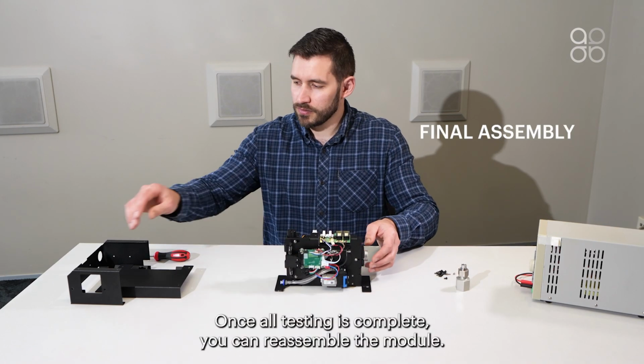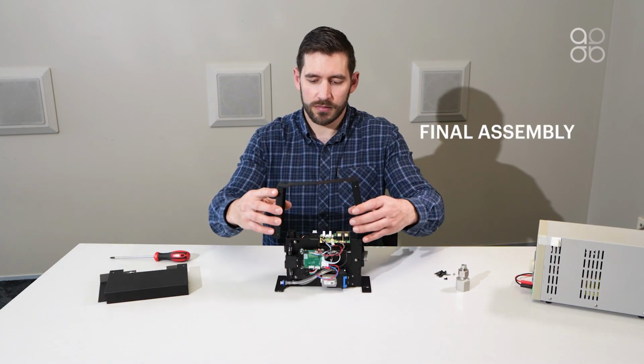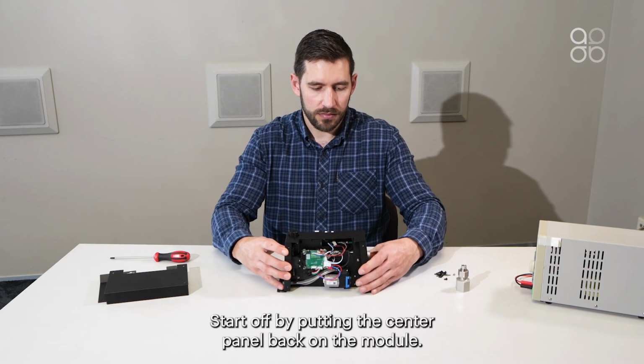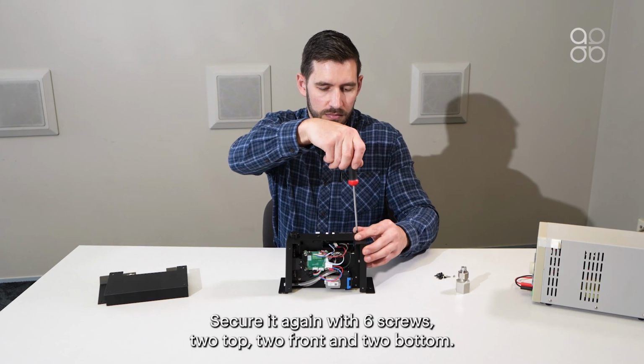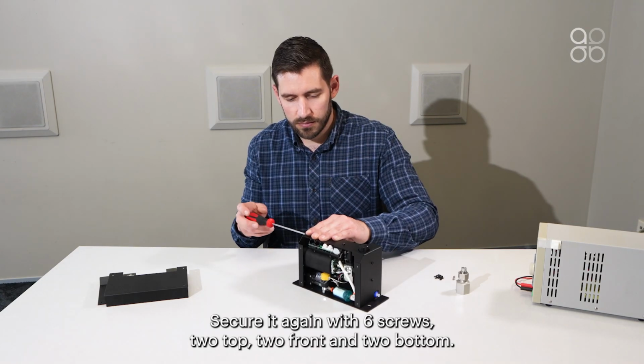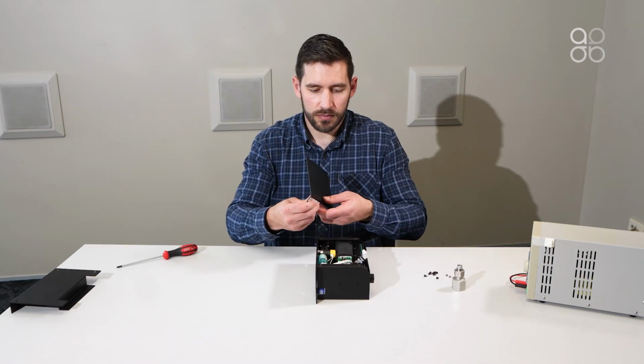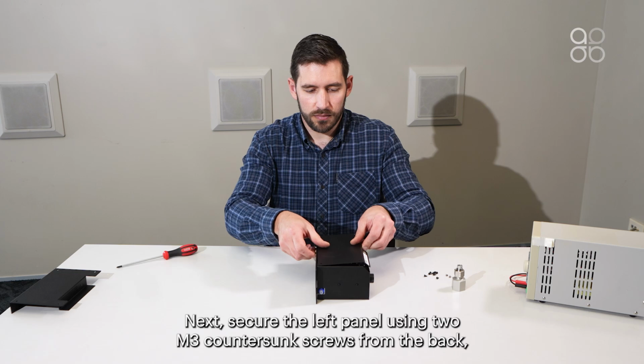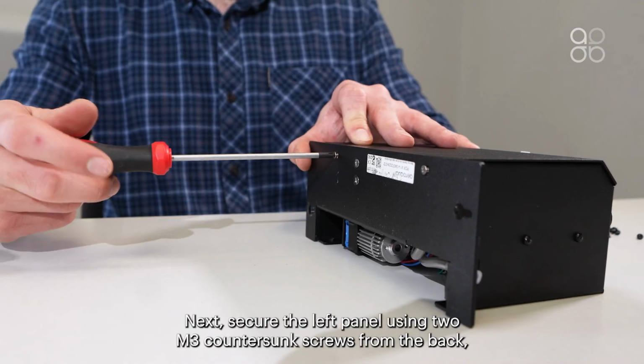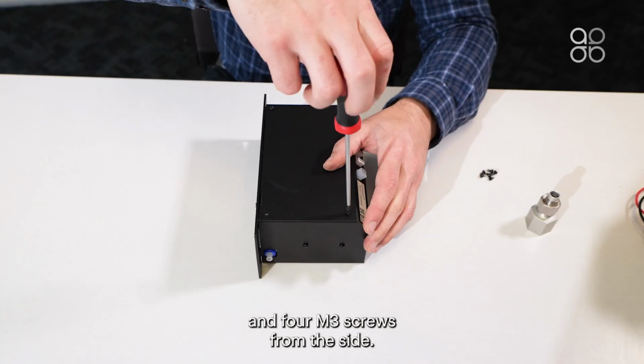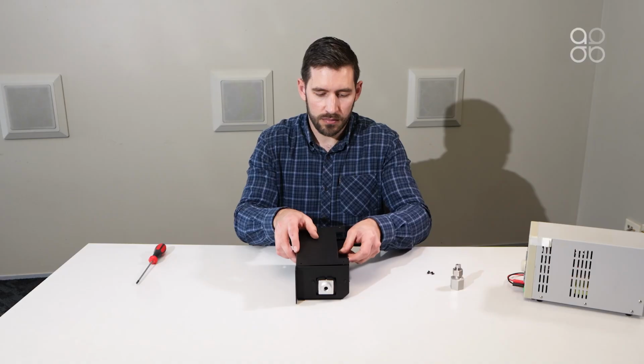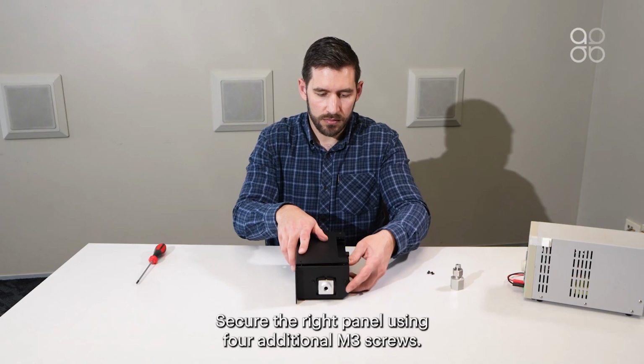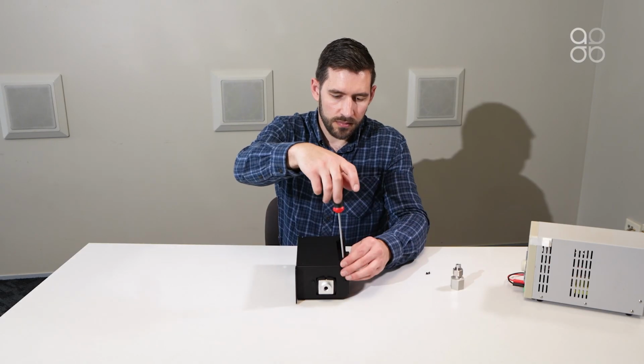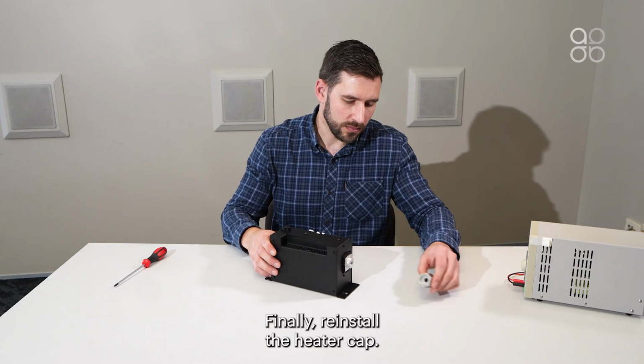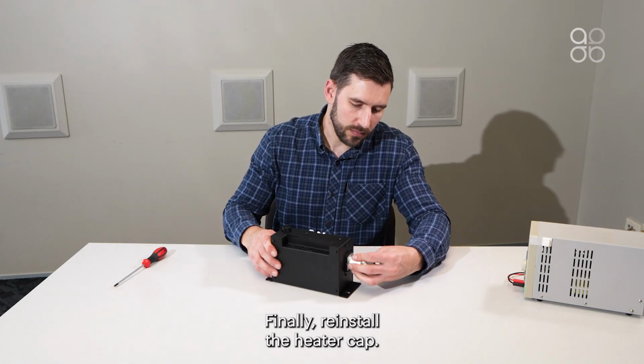Once all testing is complete, you can reassemble the module. Start off by putting the center panel back on the module. Secure it again with 6 screws, 2 top, 2 front, and 2 bottom. Next, secure the left panel using 2 M3 countersunk screws from the back and 4 M3 screws from the side. Secure the right panel using 4 additional M3 screws. Finally, reinstall the heater cap.